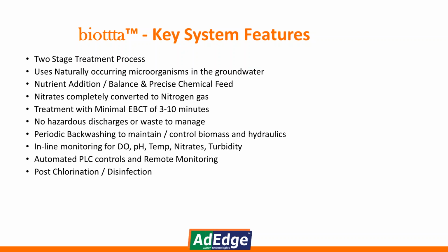We do have to backwash periodically to control the biomass and for the hydraulics. Our system does come complete with a full set of monitors for DO, which is dissolved oxygen, pH, temperature, nitrates, and turbidity. Fully automated PLC control system with the ability to remote monitor. And the final stage would be post-chlorination and disinfection.